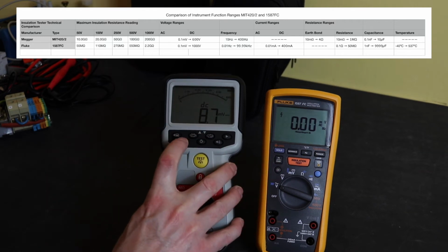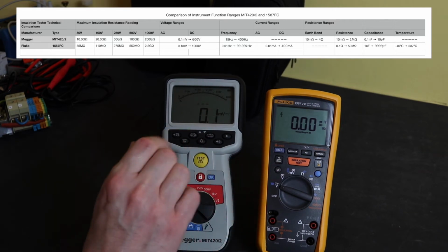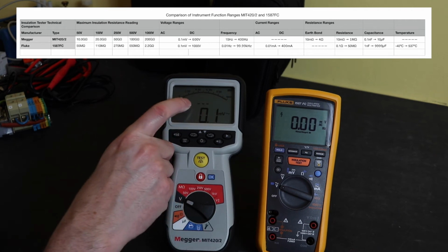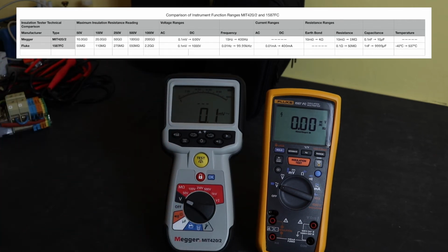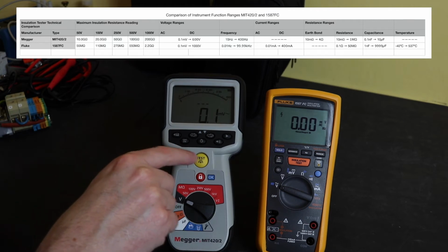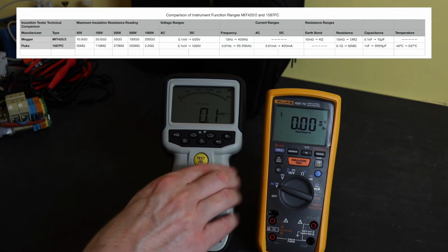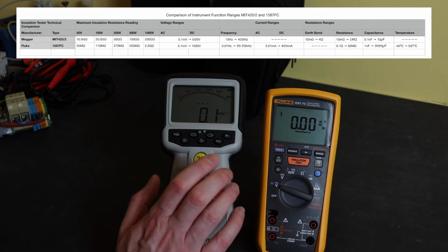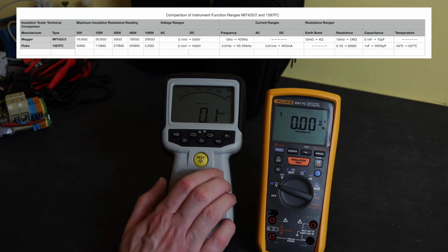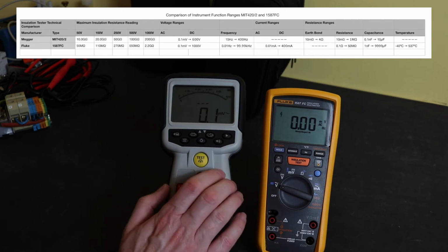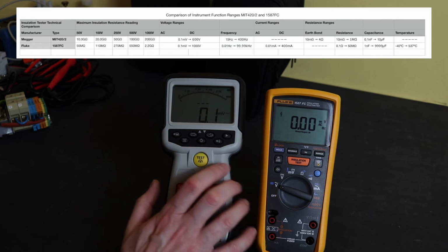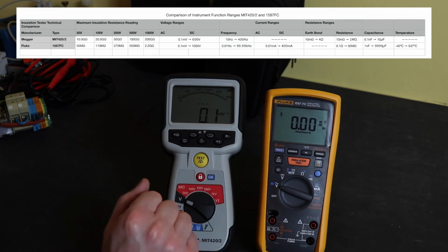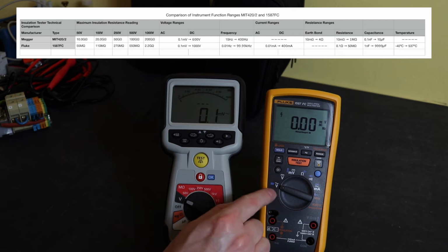For the Megger here, the Hertz is actually displayed on this top screen up here as a secondary function. You cannot get the Hertz displayed as a main function on this instrument, and it's quite a narrow bandwidth, 15 Hertz to 400 Hertz, so you've got like a permanent low pass filter built into the Megger instrument here. Whereas with the Fluke you can turn it on and off.